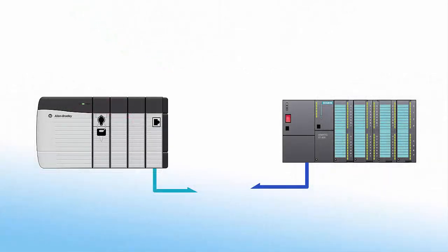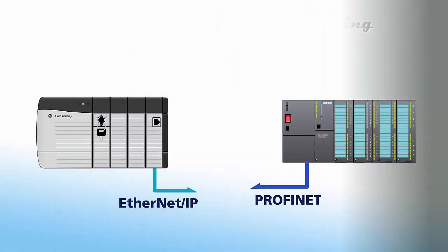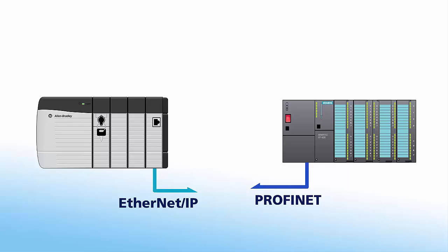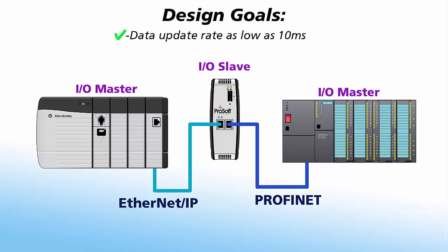In this next example, we'll examine a situation where we have two PLCs that need to do high-speed interlocking. One PLC talks EtherNet/IP and the other talks PROFINET. This application requires the communications to have extremely tight timing. The PLCs are able to make calculations and issue commands in real-time, based on data they share with each other. In applications where every millisecond counts and when the protocols support it, using the I/O messaging method is the best way to go. By configuring an I/O message on each side of our gateway, we can ensure communication speeds between the PLCs as low as 10 milliseconds.